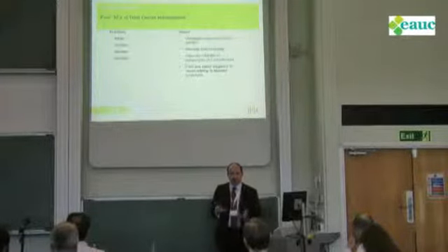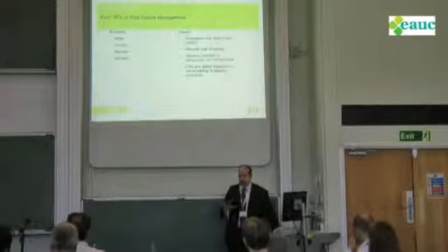Maintain your equipment. Again, sounds obvious, but people don't. They let it slide. They don't change the filters in their handling units and stuff like this. It all makes it less efficient. You're just burning money for no reason at all. And manage. If you have a sudden hotspot appear that causes a blip on your power, or causes some systems to go down, get in there and fix it straight away. The quicker you fix it, the less impact it has on the rest of your data center environment.